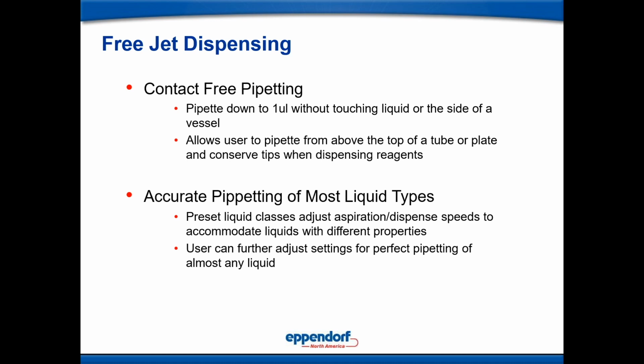Okay, it can do this in multi-dispense mode. It cannot do the blowout, but in pipette mode, and you'll always use pipette mode when you are doing super low volumes that are too small to cause a free-falling drop, the machine will push out the desired volume and a predetermined volume of air. So it's extremely reproducible. You've got to wonder, how in the world did we accomplish a CV of 1.6% with a 1 to 50 microliter dispensing tool, dispensing a super small volume down to a microliter?